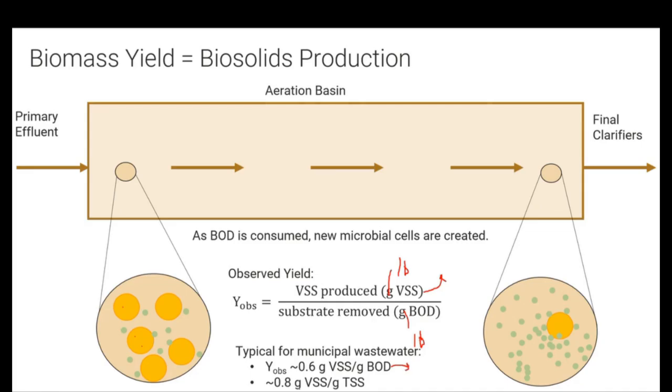And then to figure out what the total TSS or mixed liquor is, you can take your typical MLVSS to MLSS ratio, which I put as 80% here, or 0.8. I think each plant might be a little different. Jonathan, you're on. What's your MLVSS to MLSS ratio typically? About 85. Okay. What about 10 Mile? Anybody at 10 Mile know theirs?